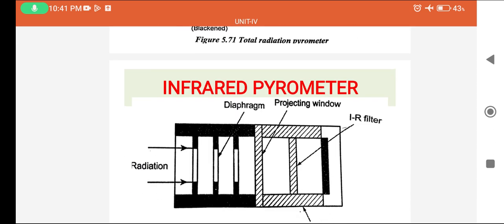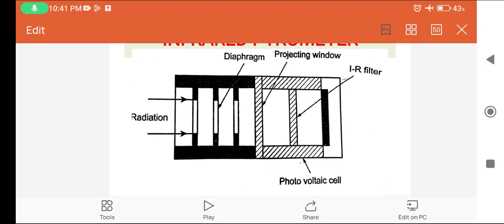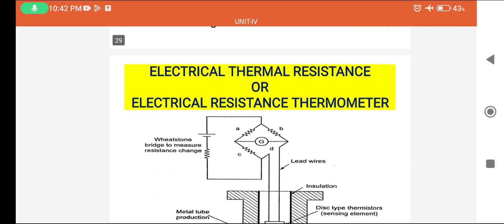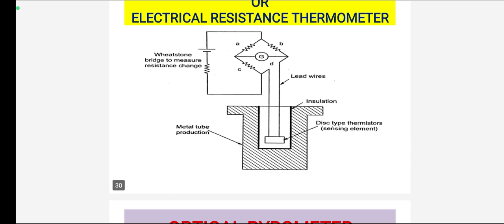So next one, the infrared pyrometer. Here the principle of the visibility of the light is used to measure the temperature. Then the electrical resistance thermometer. Here the thermometer has disc type thermistors, lead wires and a Wheatstone bridge to measure the resistance changes. The Wheatstone bridge measures small changes in the resistance, and from this the temperature is measured.